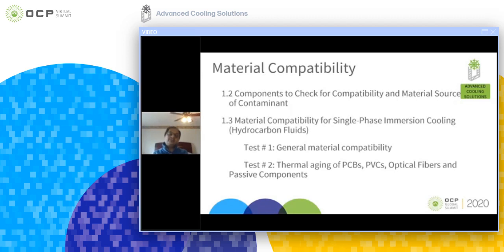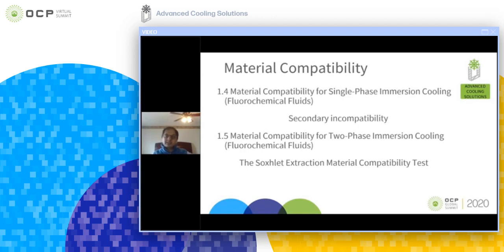So similarly, in an immersion-cooled environment, the electronics and also the supporting equipment like cables that you're putting inside may act as a source of contaminants. So we have provided a table which outlines common examples to take into consideration for such validation. With respect to material compatibility and the test methods, for single phase immersion cooling with hydrocarbons, we have provided different test methods. We have some ASTM standard test methods like D471 or D2210, which exist in the market for transformer oils, but with the right modifications, we can utilize them for immersion cooling with hydrocarbon oils.